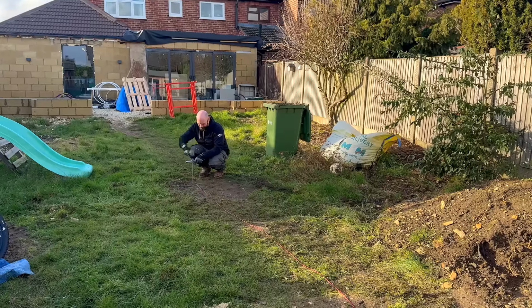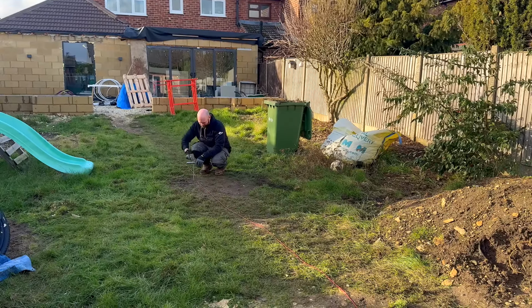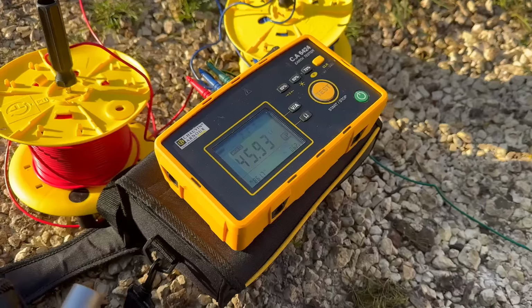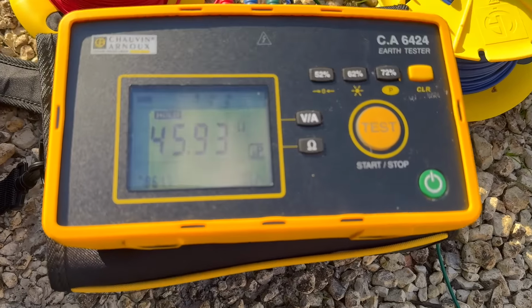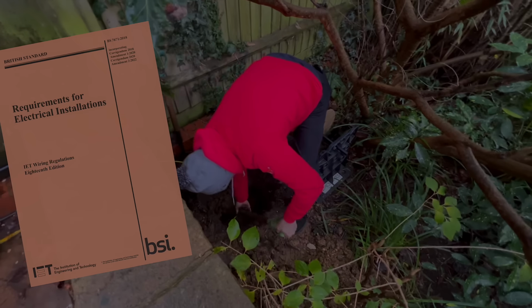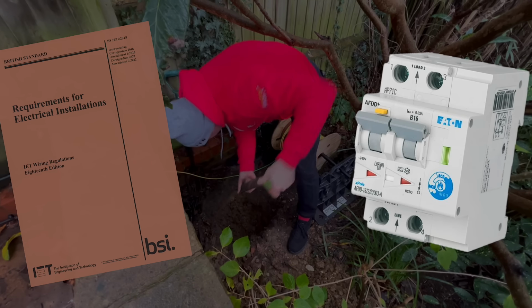Earth electrode resistance testing tells us how well the electrode connects the installation to the ground. It gives us a resistance value, often referred to as RA. That value on its own does not tell us that the installation is safe, but it is a critical part of the picture. BS7671 links the performance of the earth electrode to the protective device being used.